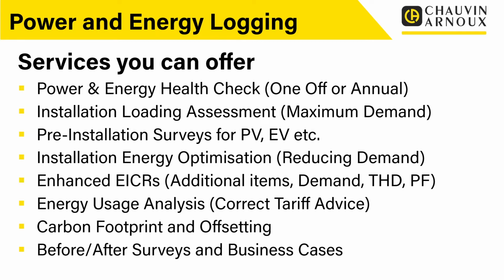Next one down: an installation loading assessment. This generally is current logging - you're measuring the current in the installation over a period of time, generally a week at least. Off that you'd have a look at an assessment of the maximum demand of the installation - how much is being drawn, how much is used out of hours, phase balancing, things like that.